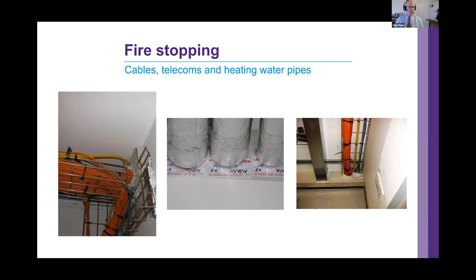Here we've got cables with fire stopping — a good standard of labelling and signing off. Check those dates when you go around. You want to see that it's a minimum of an annual inspection, as determined by the fire risk assessment. That's what good fire stopping looks like.